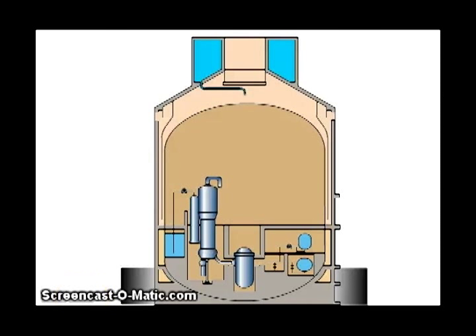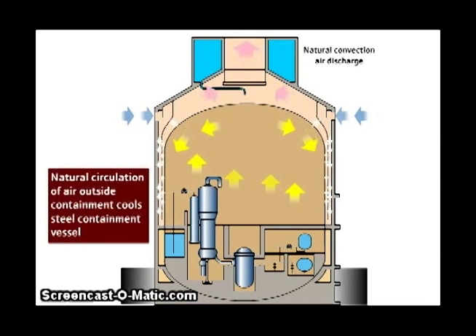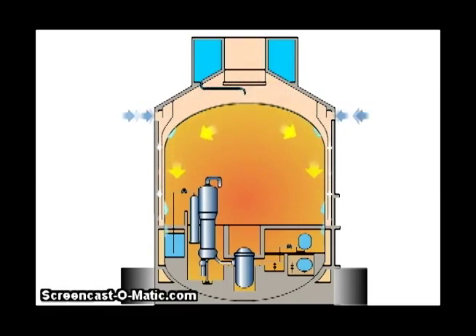Outside air and water are used to cool the top of the steel containment dome. Through the evaporation of the gravity-fed cooling lines and the effects of convection within the reactor containment, the core would remain cool enough as long as the cool tanks remain supplied. Their capacity is enough to last 72 hours, and connections are available for alternate sources as well.